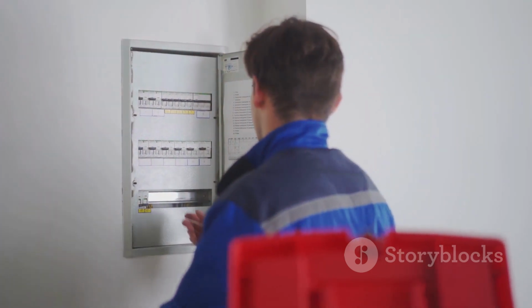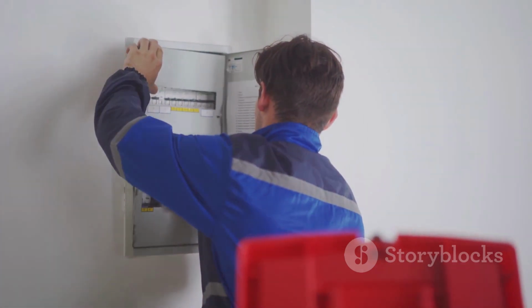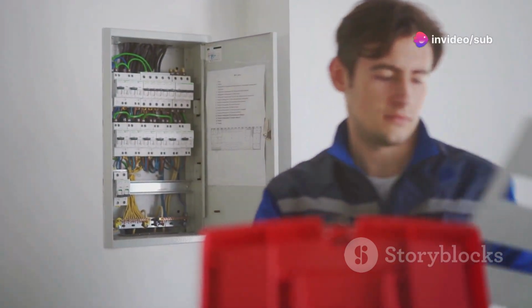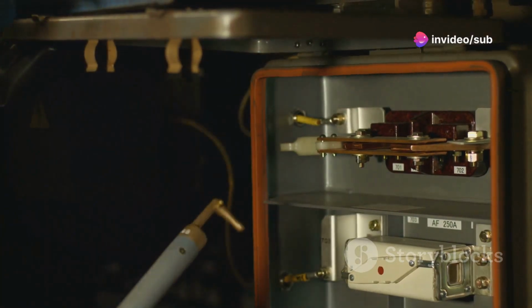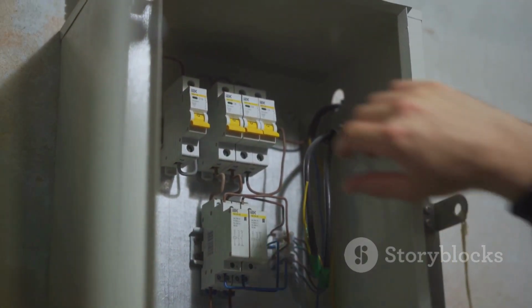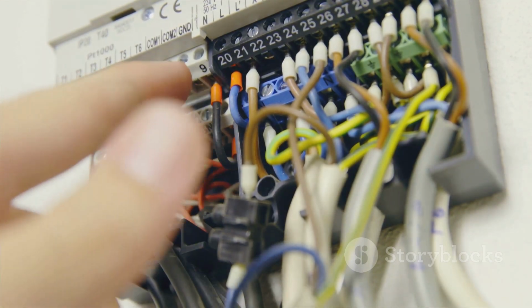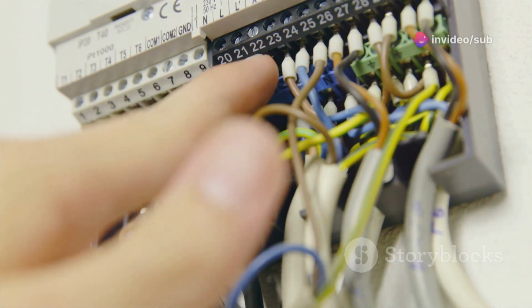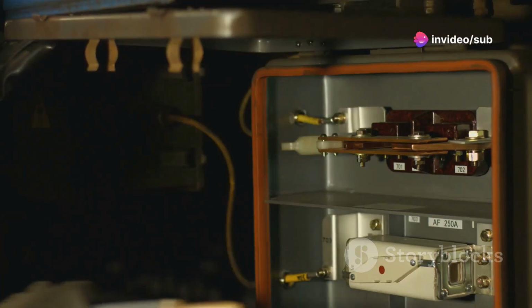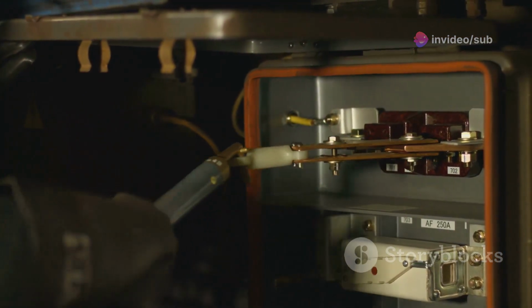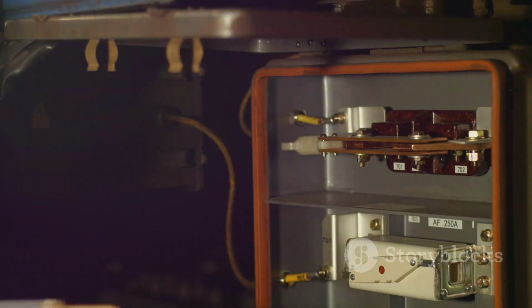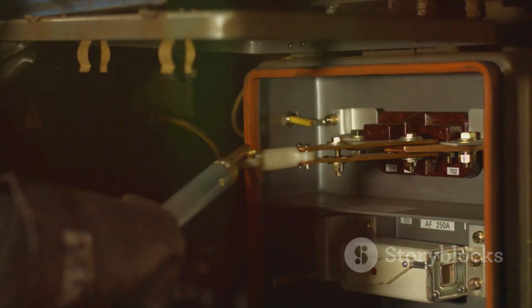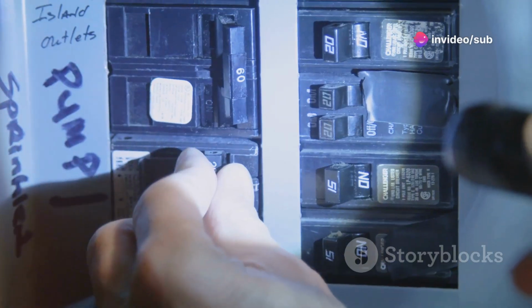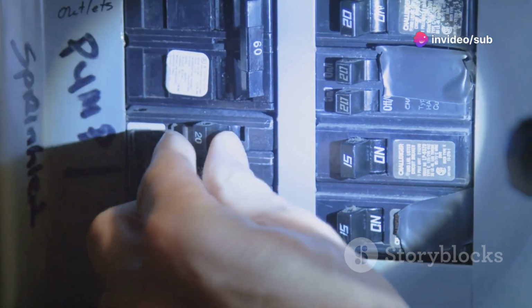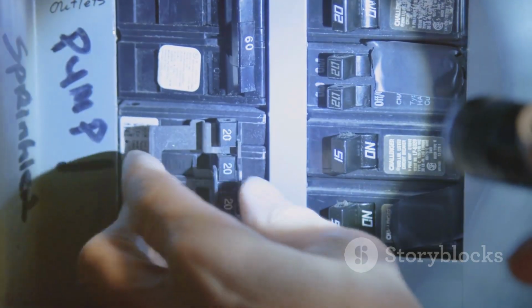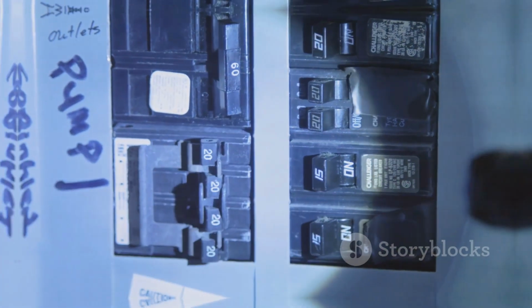Some folks wonder if the manufacturer made a mistake, or if maybe the electrician before them didn't quite know what they were doing. Others might think that more terminals mean more power, or maybe even some hidden feature. Another common question is whether it's okay to mix different wire types or sizes in the same terminal. People often want to know if they can feed 2 circuits from one breaker, or if it's just for convenience. Some even ask if you can use a multi-terminal breaker to bypass a crowded bus bar or to piggyback extra circuits. These are all really good questions. Understanding the answers can help prevent mistakes and, more importantly, keep your wiring safe and reliable.